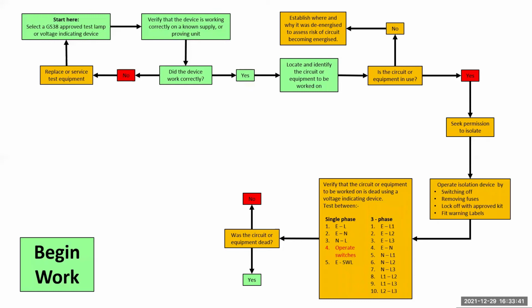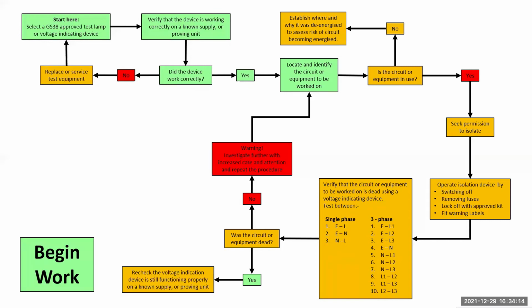I cannot even begin to tell you how many times I've been assessing and I've been able to gently knock the toggle off because it was never on properly in the first place. Don't forget that it's traditionally 3 tests on a single phase circuit and 10 tests on a 3-phase. A lot of people get caught out when testing a lighting circuit as they forget to operate the switch and test the switch lines. So I've put this in as a step so that you don't forget it. If the circuit is not dead, proceed with extreme caution. You could now be in a very precarious position as you have access to live parts.